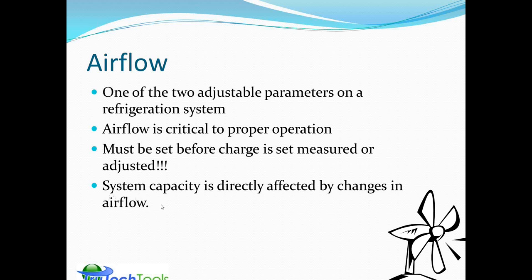System capacity — how much the system is able to cool, heat, or dehumidify the air — can be directly affected by changes in airflow. That's where maintenance factors come into play. If filters get dirty and you choke down airflow, you can affect system capacity, get a blocked or frozen coil, and see overall poor performance and poor dehumidification.